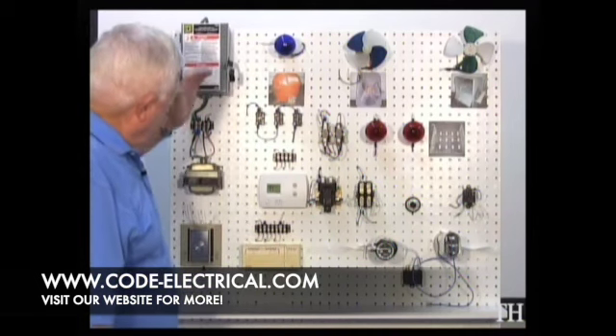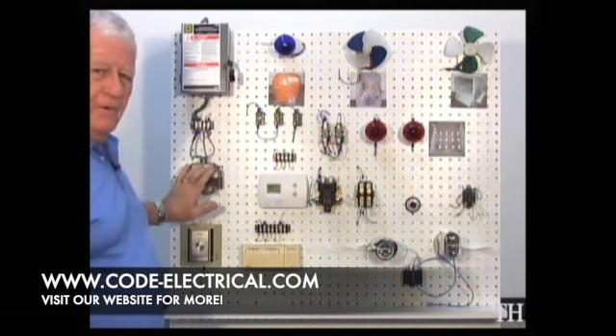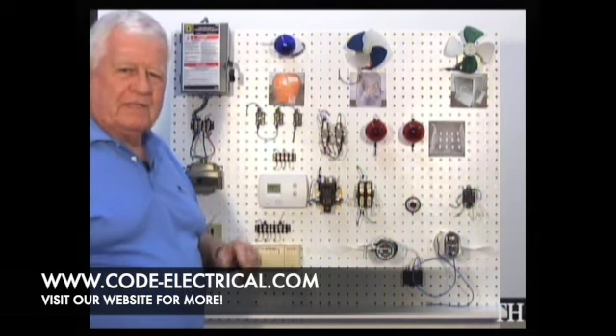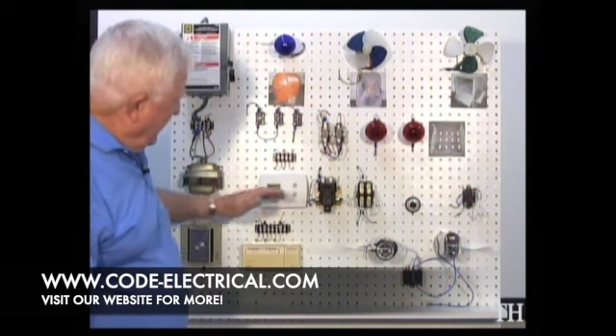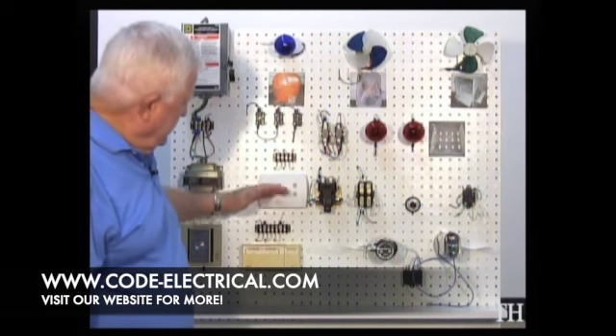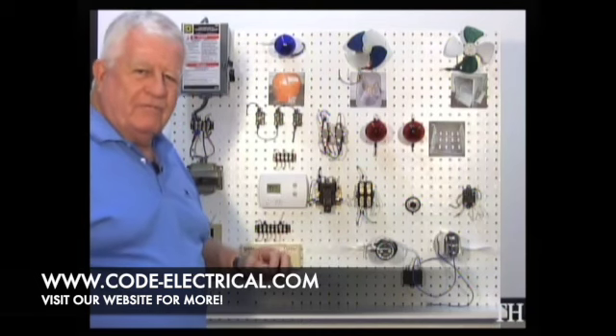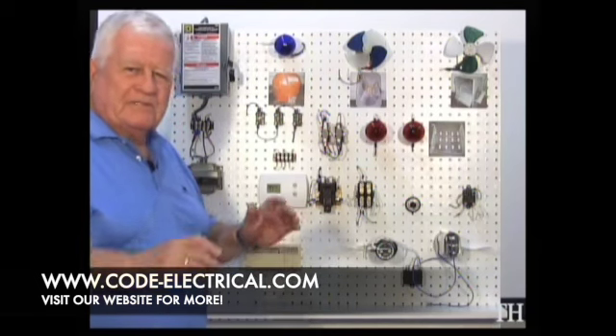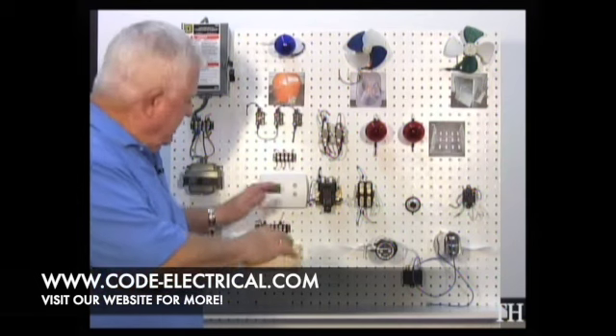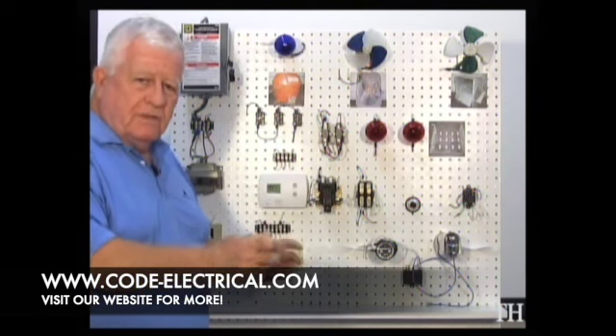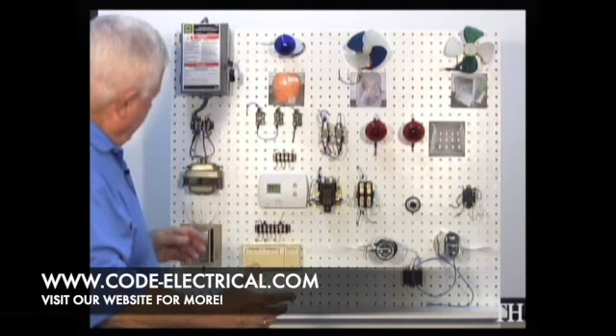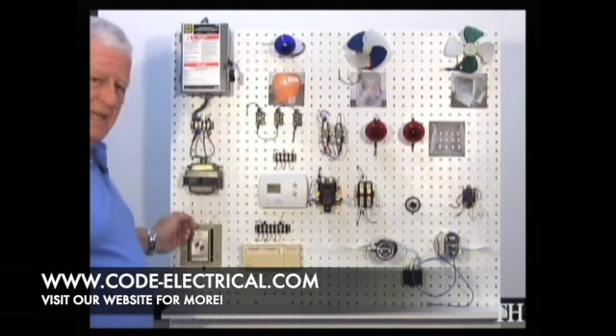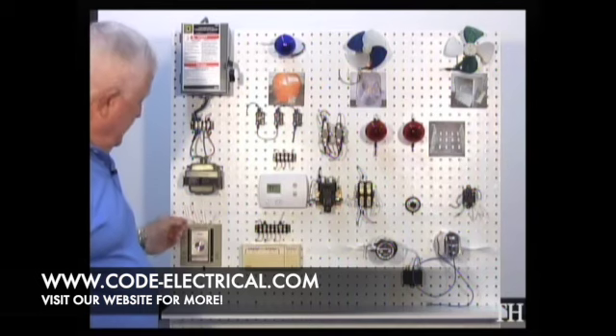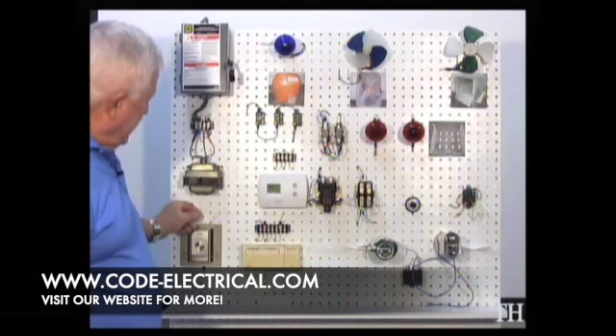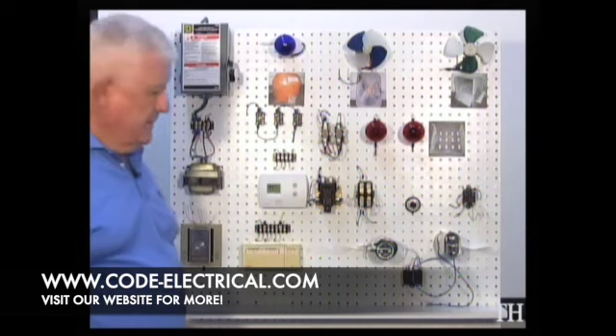But what I'm doing, I'm bringing my power into my transformer. Now it's a 24 volt transformer for the simple reason we're coming over to our thermostats, and you can see here we don't want 240 volts on our thermostat. We want something safer, a lower voltage, because people are going to be touching this and adjusting it and flipping switches, has arcing, etc. So you can see here as a technician, and eventually you'll have this memorized: the red wire's power, the yellow will be air conditioning, the white's heat, the green's your fan motor.